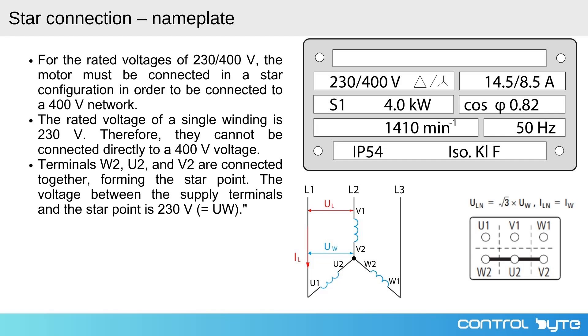In a star connection, each winding of the motor is connected in such a way that the end points of the windings labeled as W2, U2, and V2 are joined together to form a common star point. The other ends of the windings are connected to the supply phases L1, L2, and L3.